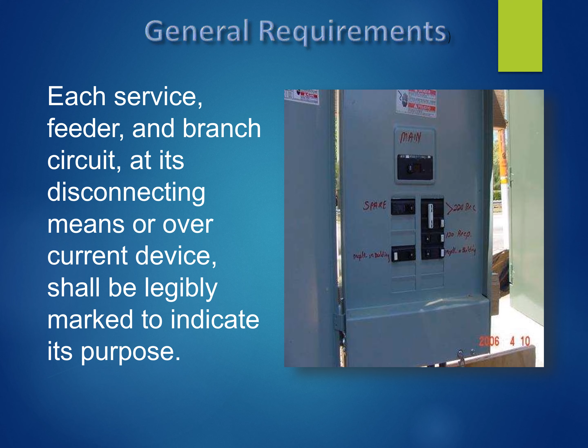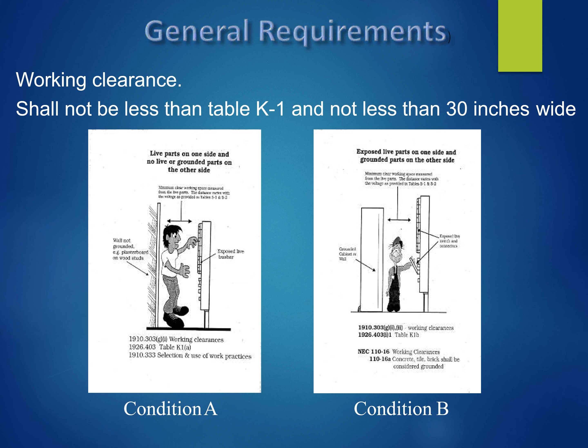Here is the illustration for the working clearance for the equipment. You see condition A, the working clearance in front of the equipment is not adequate. Meaning if there is electrocution here, you will notice the person there is unsafe. So this is just an illustration to maintain unobstructed clearance in front of the equipment. If you are installing electrical equipment, ensure you maintain unobstructed clearances in front of and adjacent to that equipment. This is the illustration of this.